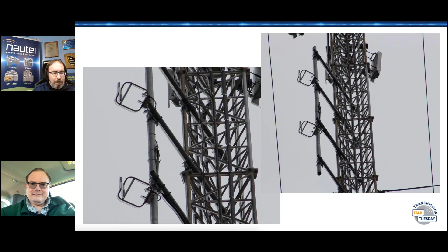That ties into what Brad had asked about cable wear in the advanced questions, and I'd posted a picture related to this on a slide deck or Facebook. At one of our sites, we had a reflected power issue to the point the transmitter just said, I'm not doing it. We brought in a tower climber, and under one of the round member adapters, the cable clamps on the 7/8 going up the tower - fortunately it was close to the antenna, which helped - there'd been enough wind and cable motion that the cable had totally worn through both the jacket and a good portion of the outer conductor, so the shield. It was wearing through the phenolic inner when we found it, and every time it got a little moist, impedance changed significantly. Transmitter said, nope, not doing it. So that one required a tower climber.